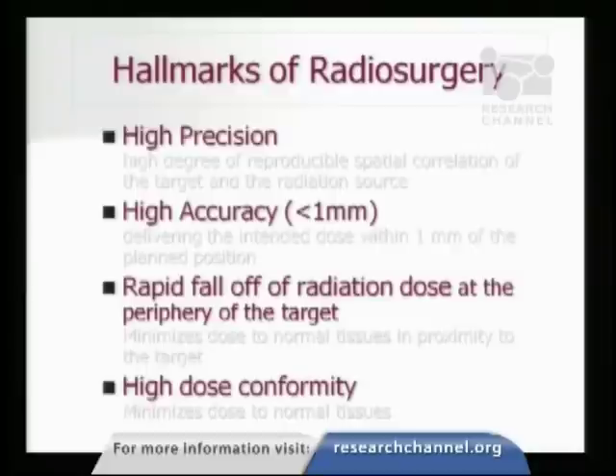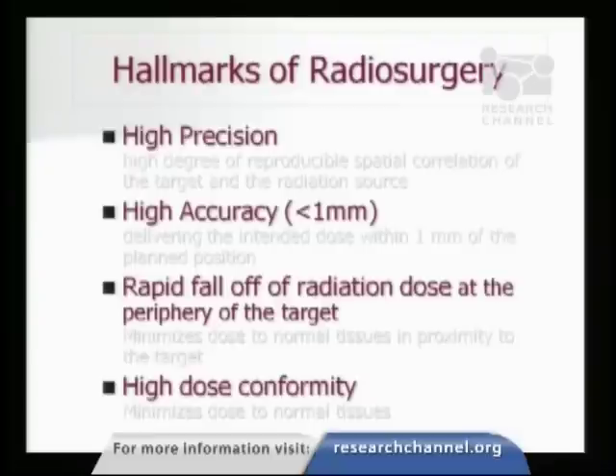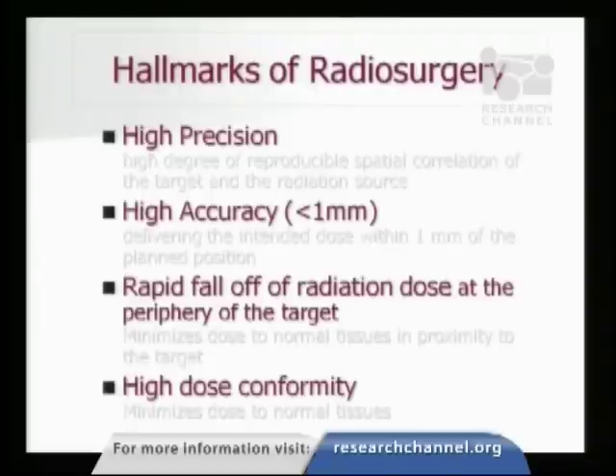The main hallmarks of radiosurgery in general — and CyberKnife is just one form — is that it's highly precise, meaning one can continue to deliver a similar dose to a similar target in a very precise way. It's very accurate: where you want to deliver the dose is where the dose goes, within an error range of about one millimeter. There's rapid dose fall-off at the edge of the target, and it's highly conformal — meaning the dose can conform to the shape of whatever regular or irregularly shaped target you have.